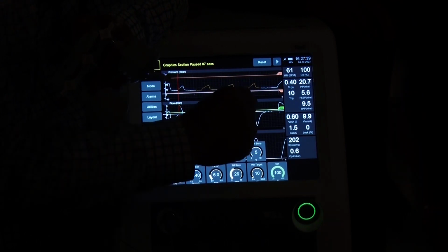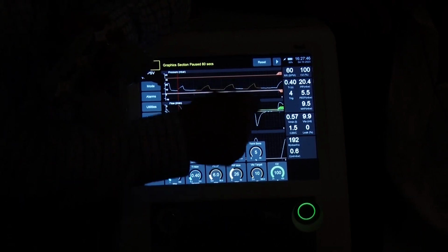So I tend to set, if you get something like this, that's perfect. But if not, I'm just wanting to see a line that is not quite straight, it changes sign. And then your I time's probably okay. If your I time's too short, it goes straight down. And you can see that it's subtly changing here.